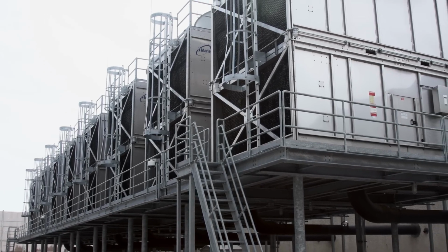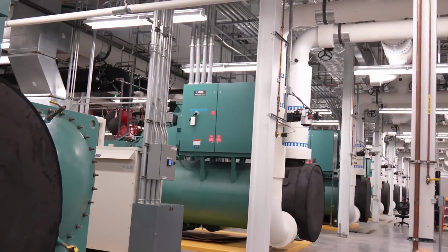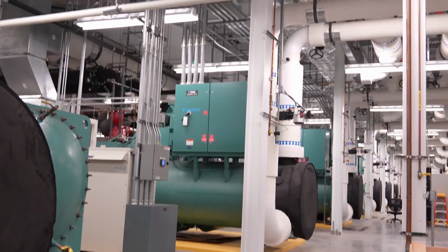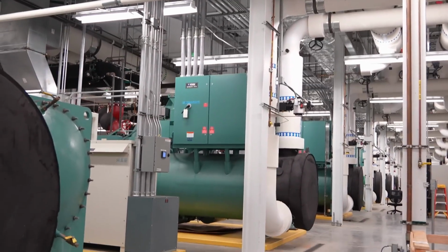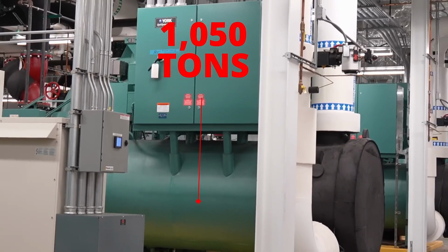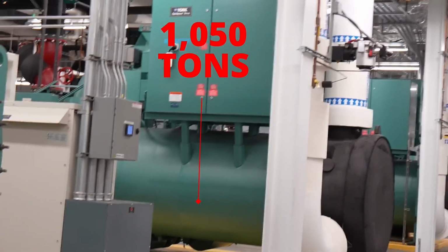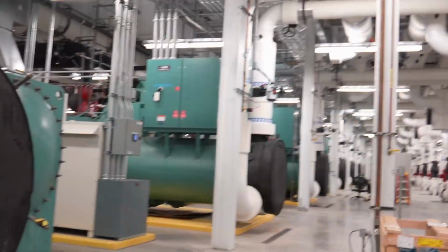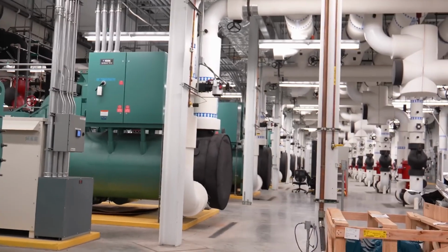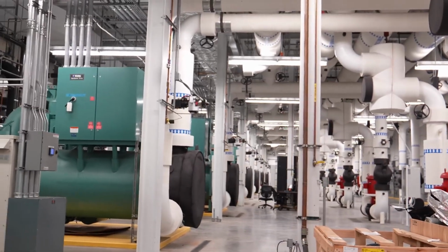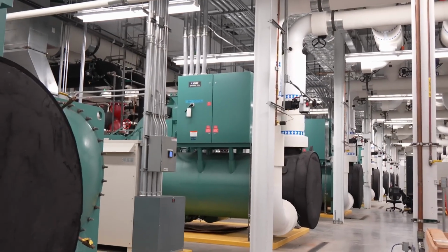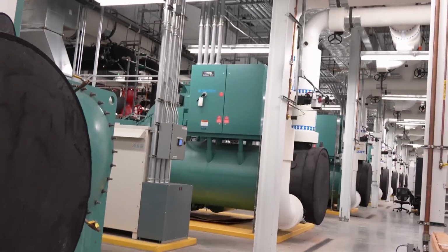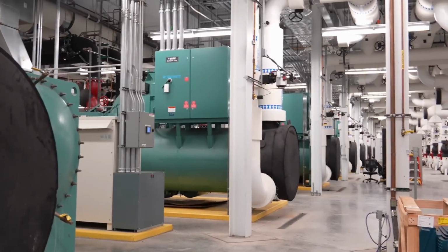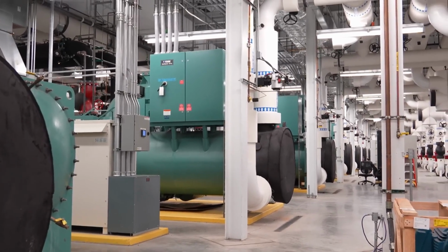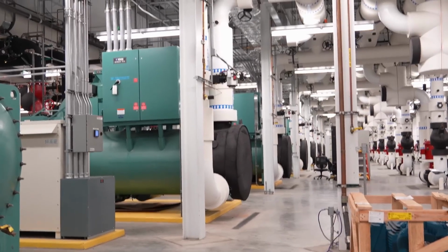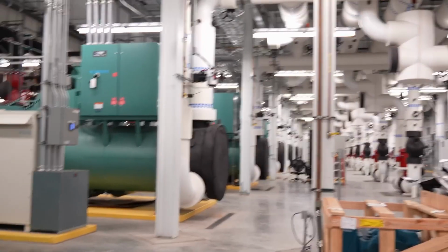For scale, a normal residential air conditioning unit is usually 3 to 5 tons. Each of these green units here is 1,050 tons. There's a redundant number of them so one can take over if we're at full load, but we're usually not, so maybe 2 or 3 are on depending on heat generation, and the load rotates across them to balance the hours. Otherwise you'd wear out half the units while the other half stayed almost brand new.